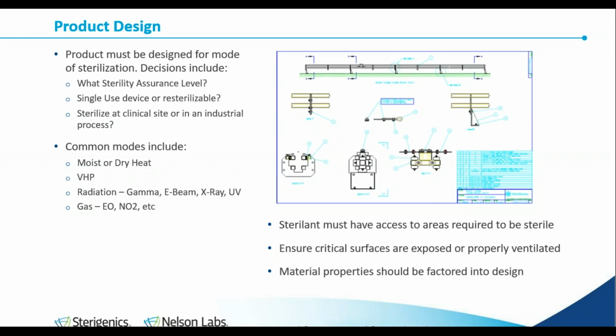We have to make sure in the product design that we've ventilated everything that does require sterilization properly so the sterilant can get there. Obviously, for gas and thermal processes, there may need to be some sort of ventilation; for a radiation process, perhaps you don't have to worry about that so much. And then the material factors need to be figured into product design. And honestly, more than anything else, materials and the product itself inform what choice you'll ultimately have to make for the modality of sterilization you choose. If you move on to the next slide, Martel, we'll go into more detail.